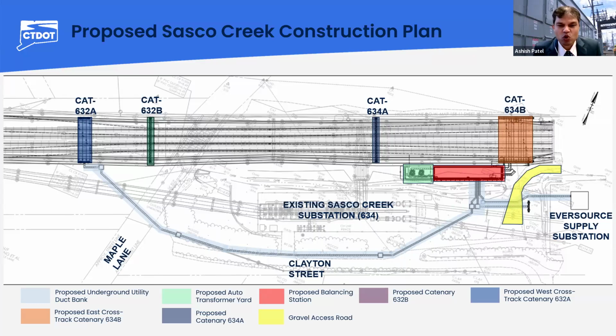The entire site is owned by the state of Connecticut. The installation of the proposed balancing substation building requires flat ground. The proposed site has an elevated ground. The new balancing substation foundation will be designed as a retaining wall to compensate for the existing ground elevation difference. The new walk-in type wall will be constructed for placing the new balancing substation enclosure and pulling cable in and out. The balancing substation will be constructed as a prefabricated walk-in type metal enclosed building. It will house various traction power equipment.